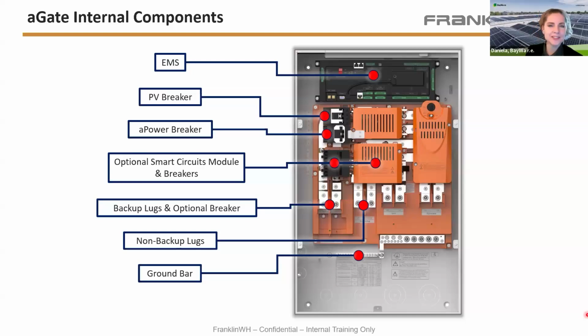And then I do, sorry, I do see that. No problem. I do see that. Yes, we do have the ability to connect more than 80 amps of PV to the aGate. We have an external component called aPbox, which is a remote PV curtailment and monitoring device, which allows us to connect an additional 160 amps of PV to the backup circuit. So if you're thinking about that in kilowatts AC, it's roughly around 45 kilowatts AC. So we are very stackable, not only on the battery side, but also on the PV input. Okay. Yeah, just pause me if more questions come up.